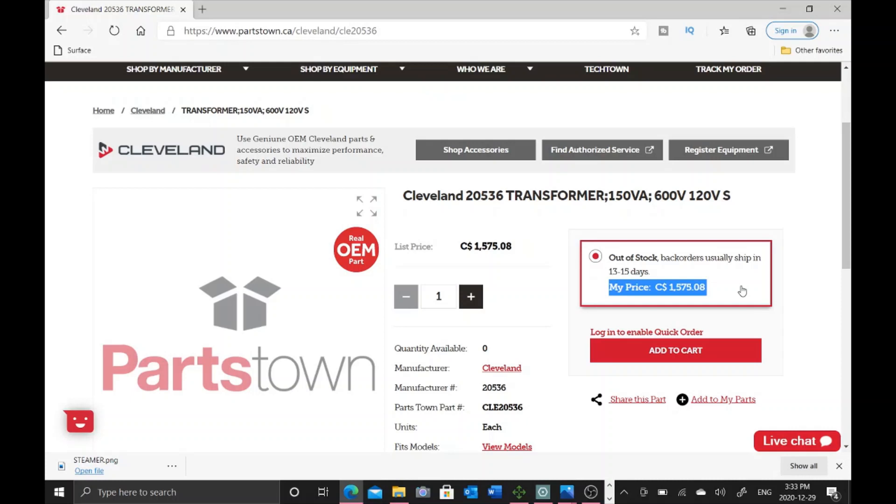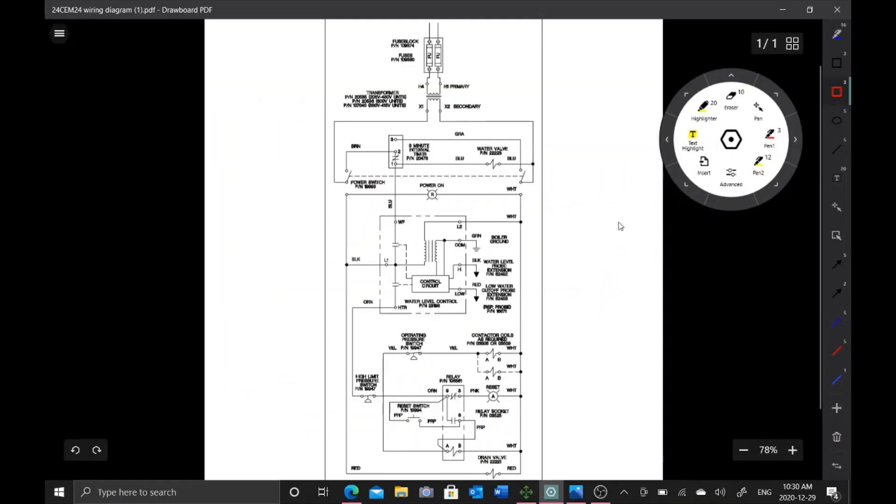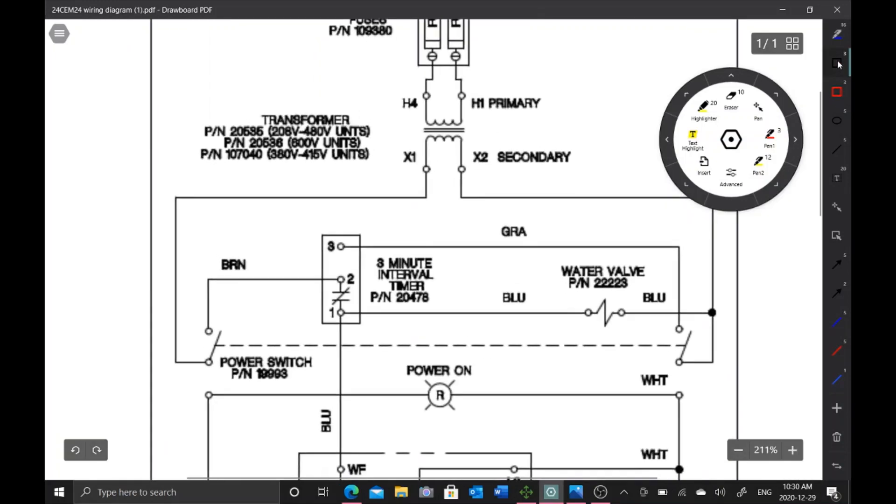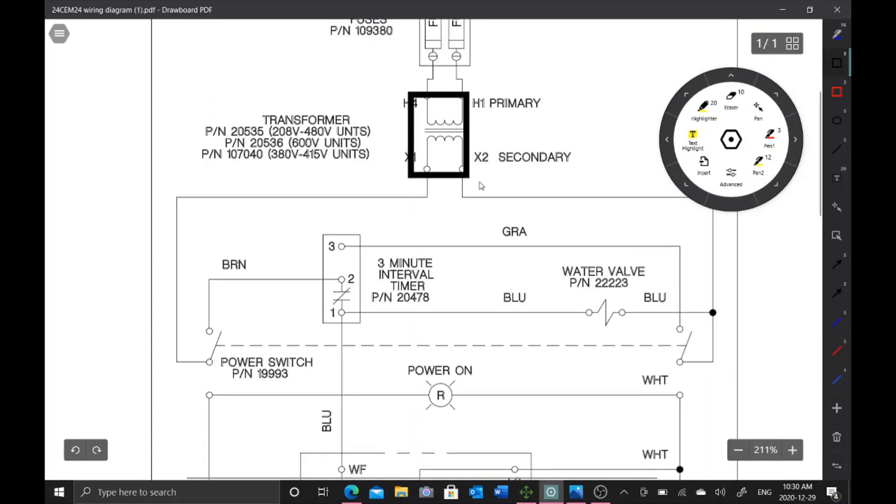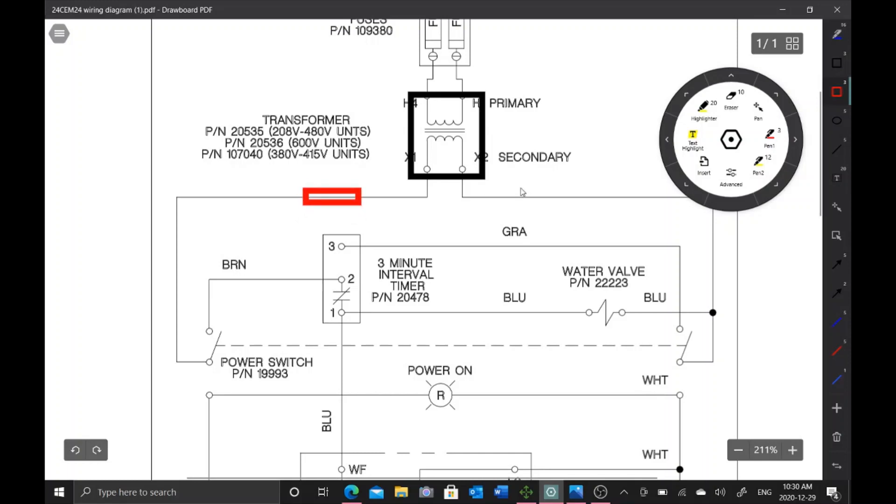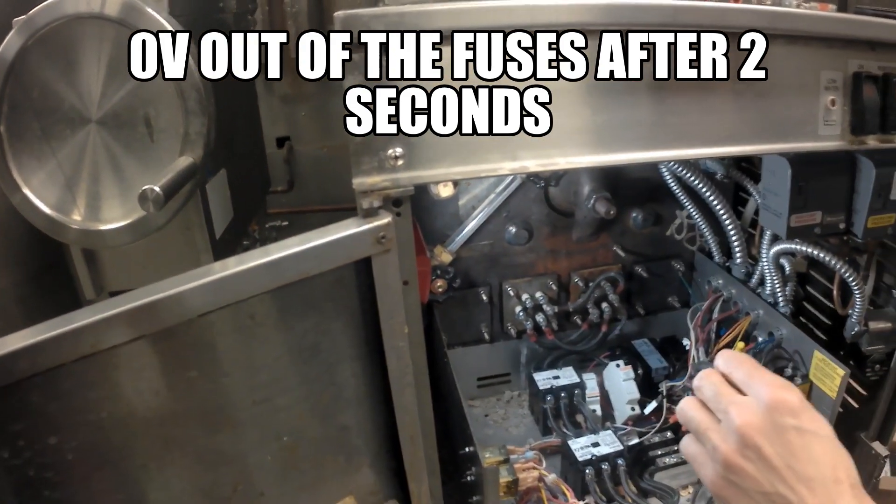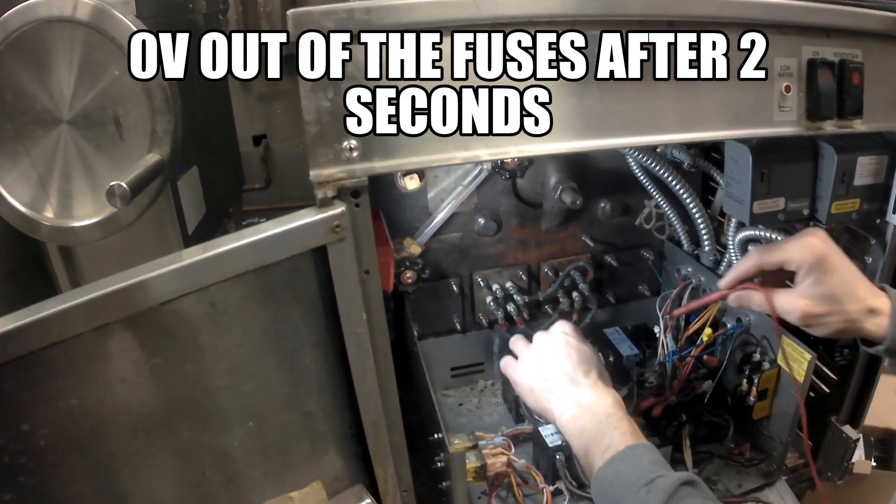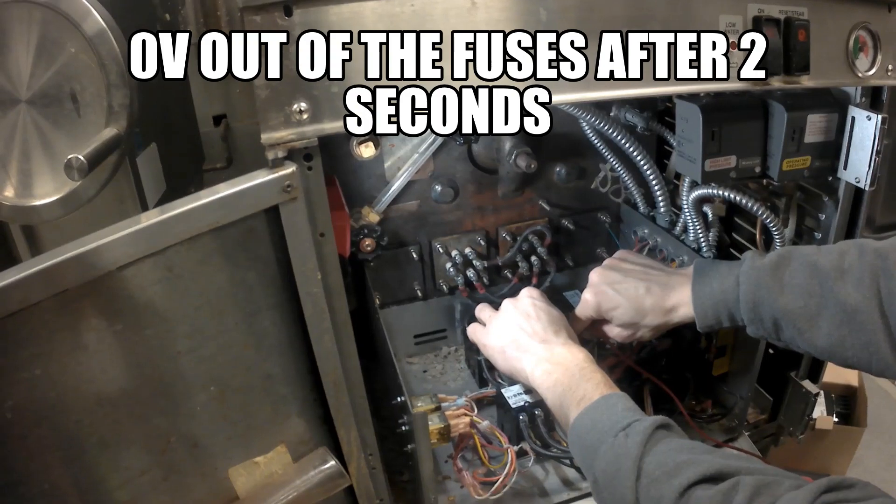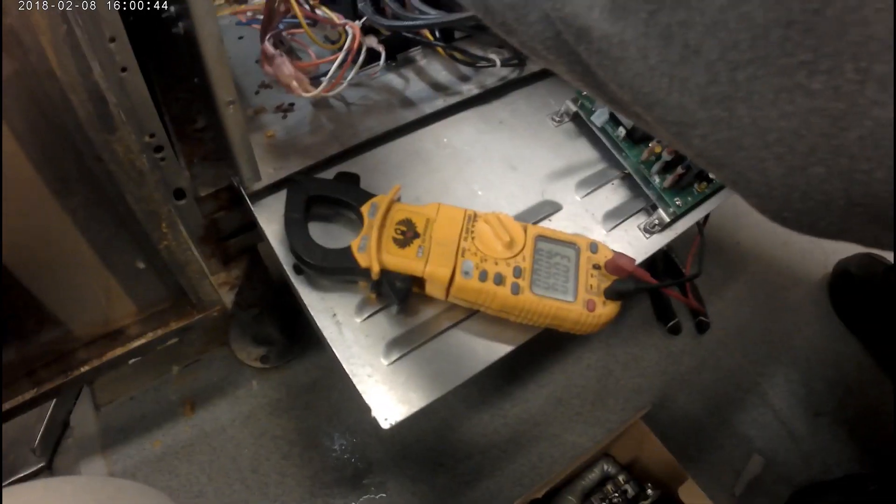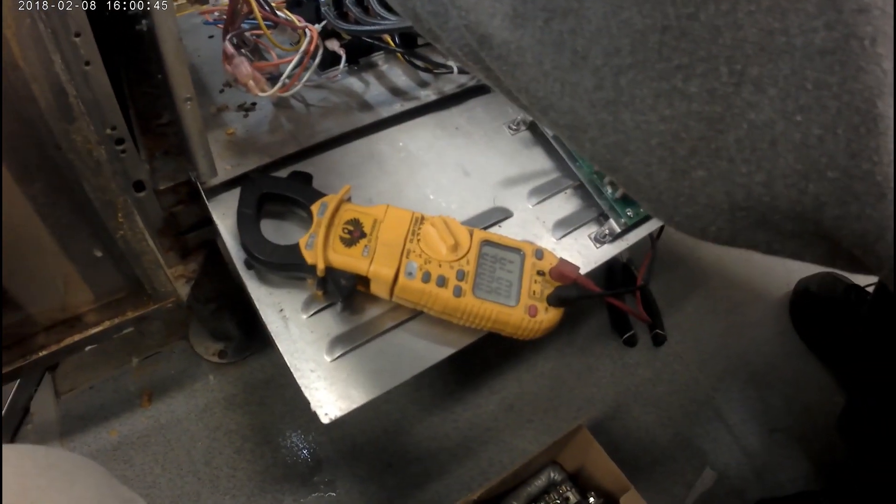Here's our schematic. Our transformer that keeps blowing is this guy right here. What I've done is installed two fuses in line, one here and one here. Whatever's shorting out our transformer, it's going to take out either side of these fuses and then we save this very expensive transformer. As soon as I turn the switch on, after two seconds I go from 130 volts to zero volts coming out of that fuse.